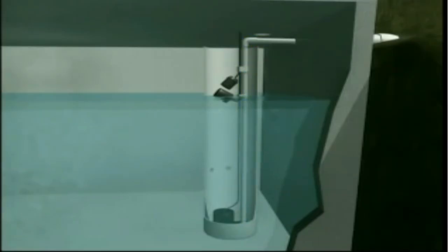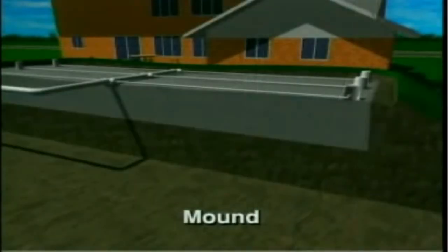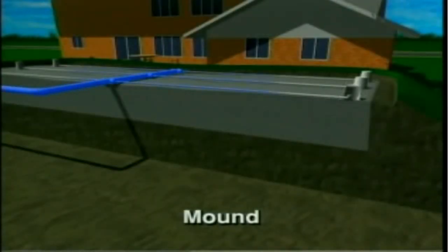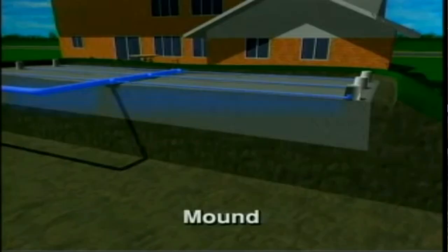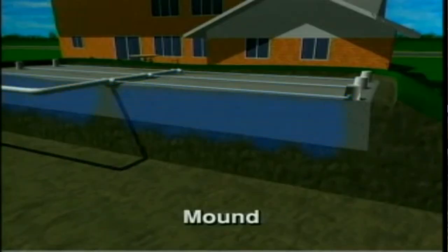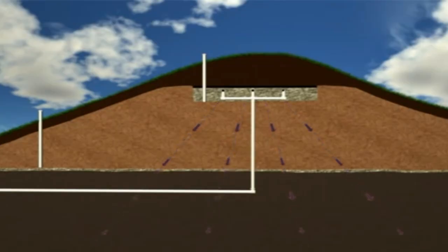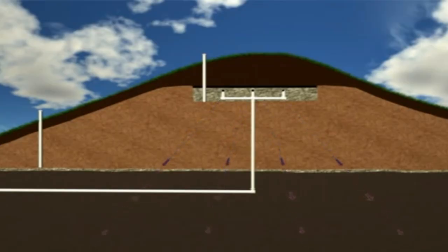The pump then pumps a predetermined amount of effluent up to the sand mound, located above ground level. Once the level of the effluent in the dosing chamber is reduced to the level of the off float, the pump automatically switches off and stops pumping.